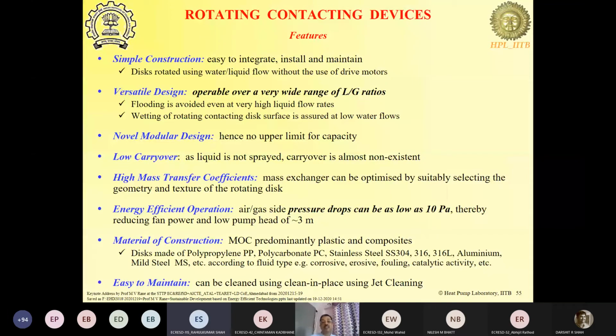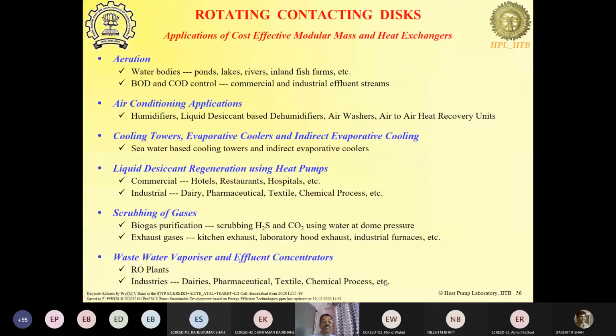So you can have a very wide range of L by G ratio, that is the liquid to gas ratios. Okay. And no limit in capacity, very low carryover, high mass transfer coefficients because of the rotation and renewal of the surface on the disk as well as the liquid disk. And then of course you have very low pressure drop because air passes parallel to the disk. Maintenance is not an issue. We can give you the disk in the material that is required for that particular process, and cleaning using a jet is sufficient.